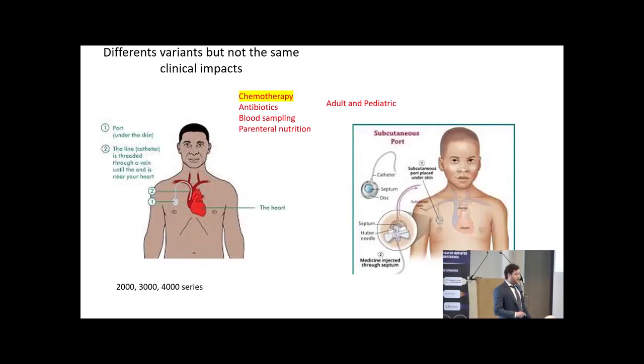And who starts first? It's not the notified body. The Australian TGA started. Red flag. I don't have it for the pediatric, and they gave them just 1 month to give the evidence. Obviously, they can't. And the device was retrieved from the Australian market. The regulatory agencies couldn't communicate with each other. One month later, it's now the MHRA, right? I want to see my clinical evidence. Where is it?